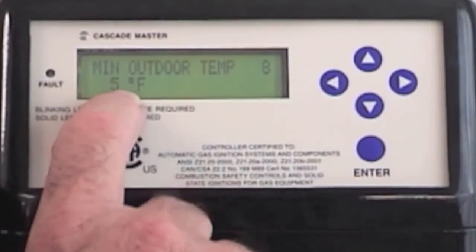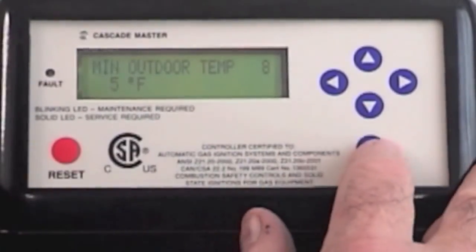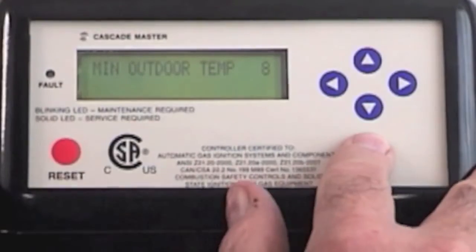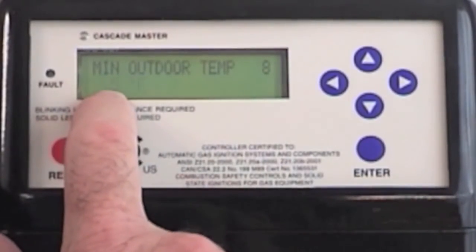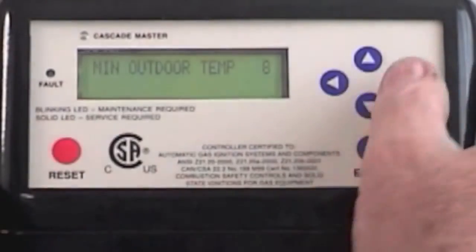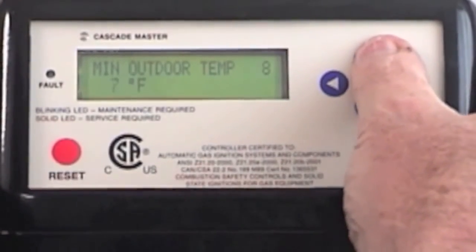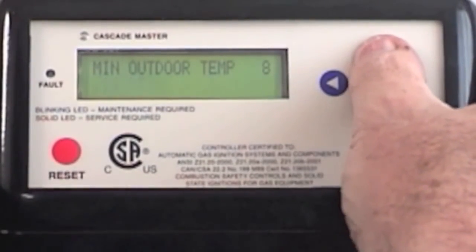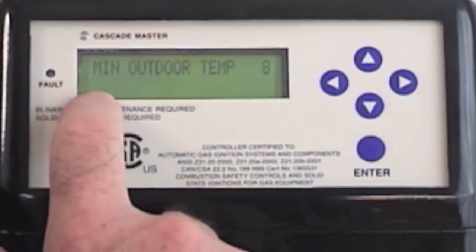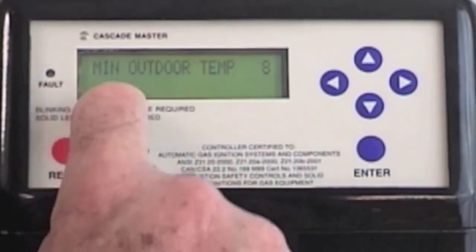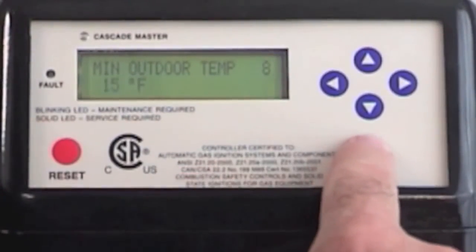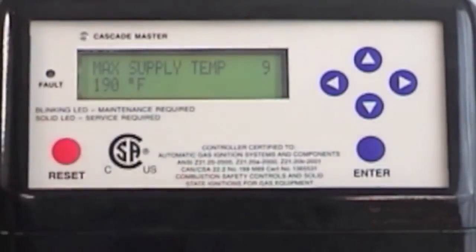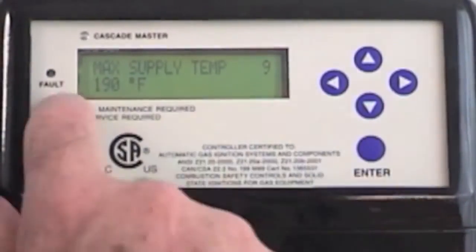Boston's design temperature is 5 degrees. I want to change that to 15, so I'm going to hit the enter button — you'll notice the 5 is flashing. I'm then going to hit the up button. I now have 15 degrees, so what I'm saying is when it's 15 degrees outside, I want my heating system to go to 180.